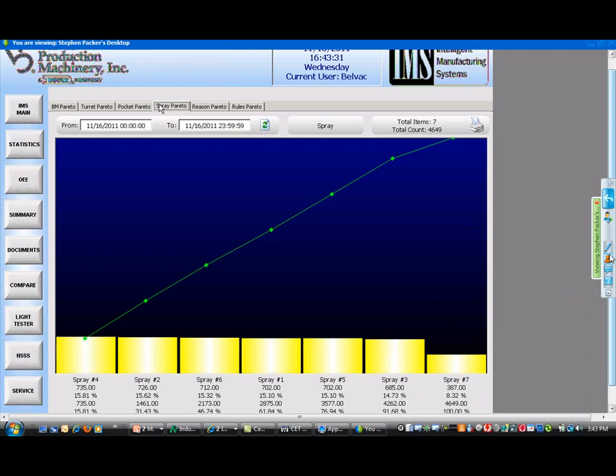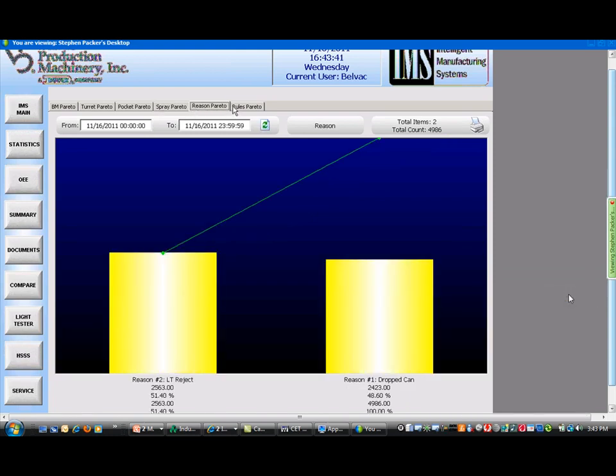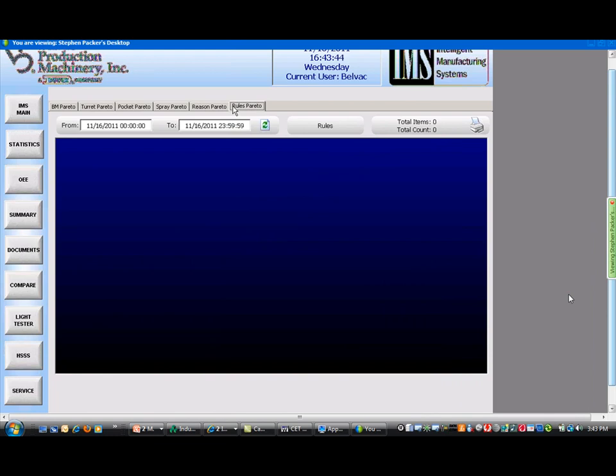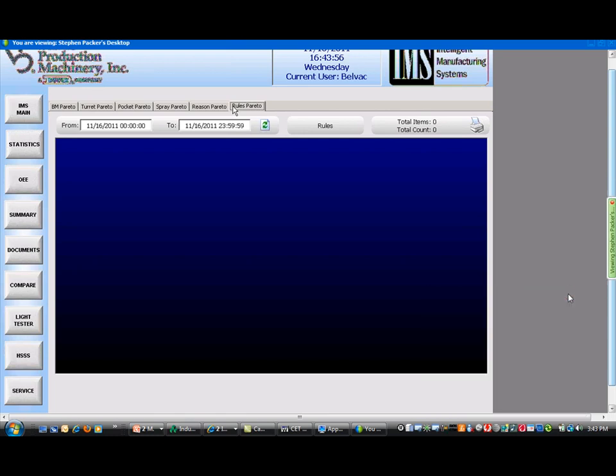We can also look at inside spray data in the same way. We can set up rules for the system — for example, if you have more than five rejects from the same turret within five minutes, stop the machine or send an email. We have a great deal of flexibility in how we make those rules, so whatever our customer requires, we can accommodate.